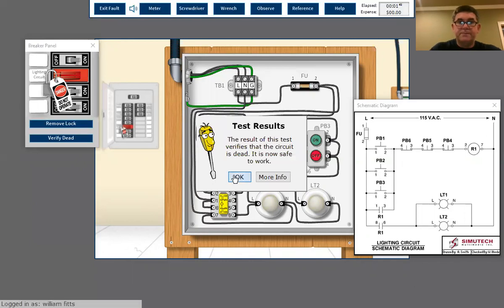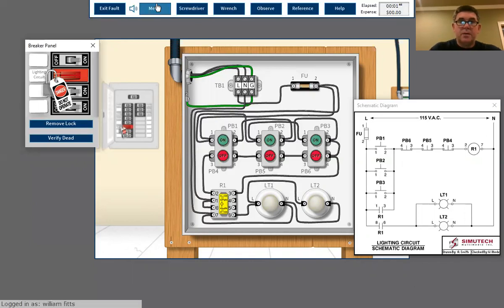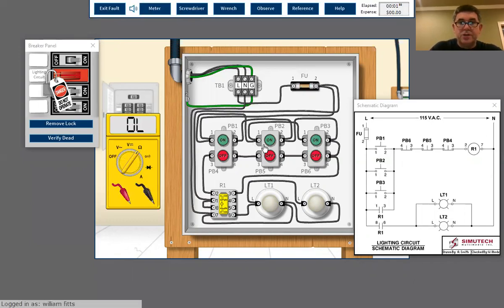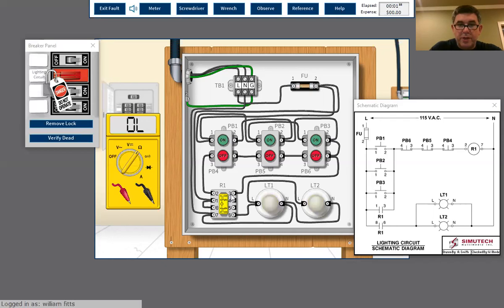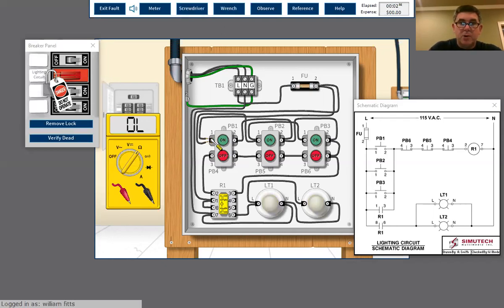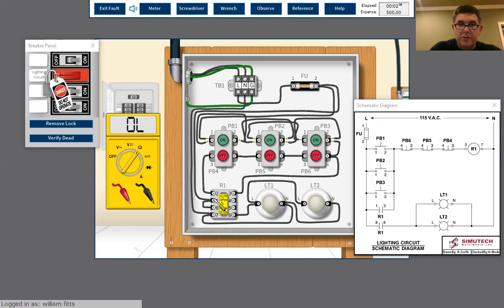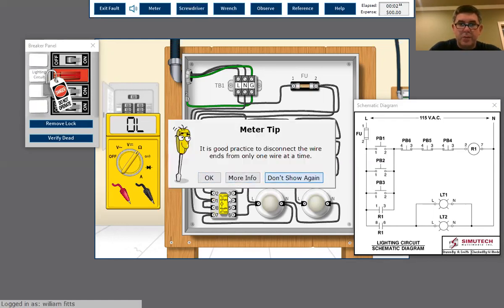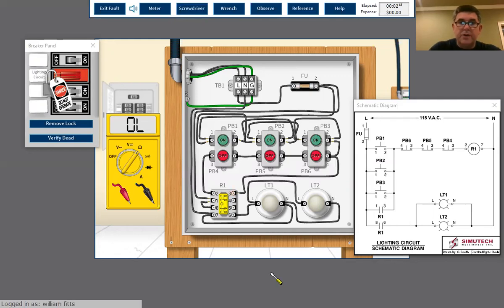Get our meter, and what are we gonna do? Check resistance because we're gonna check across these start buttons. It's either one of the start buttons or that relay between 1 and 3. Let's get our screwdriver. I'm gonna pop these off real quick because we know we got to go through them. One to three, right? So we can jump through there pretty quick. I'm gonna check from here to here.